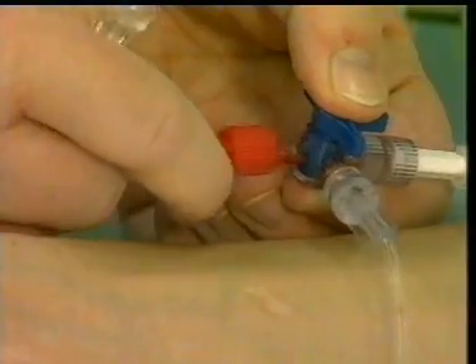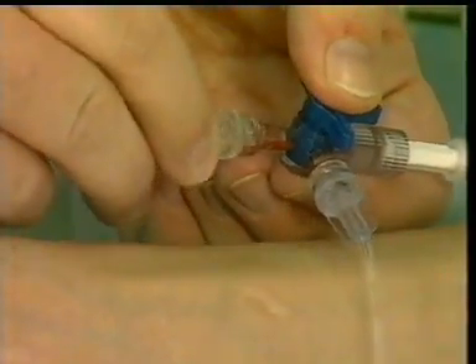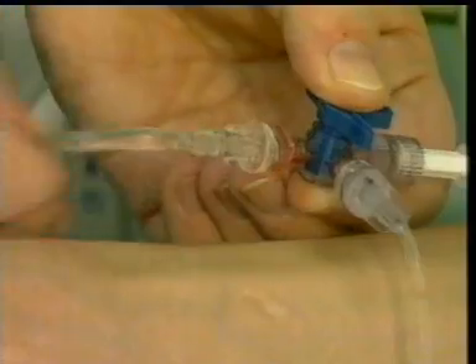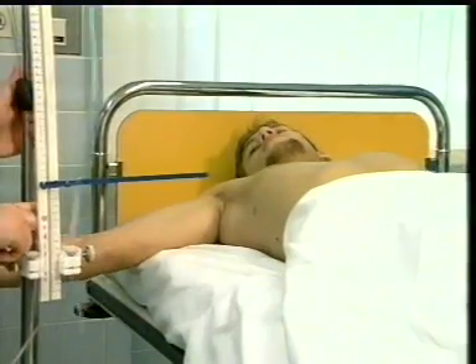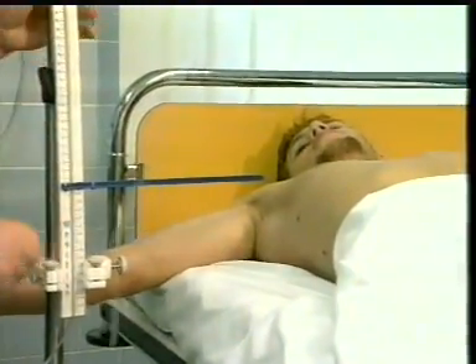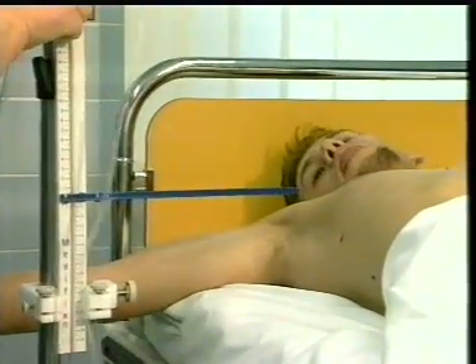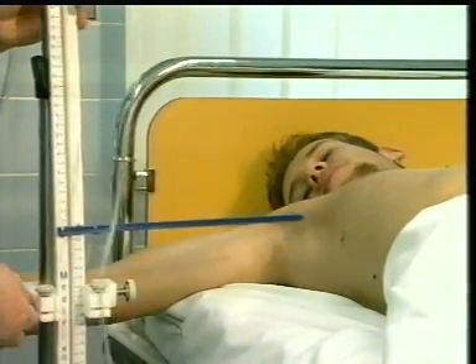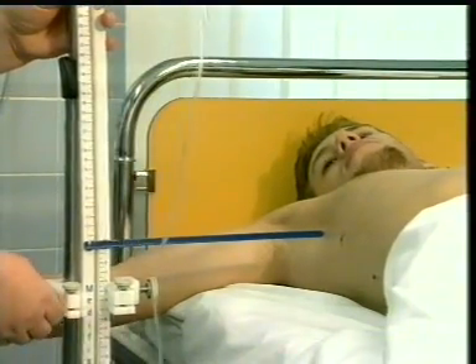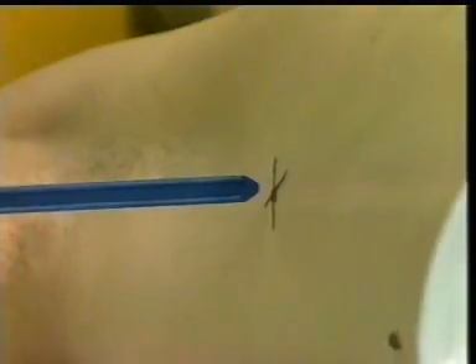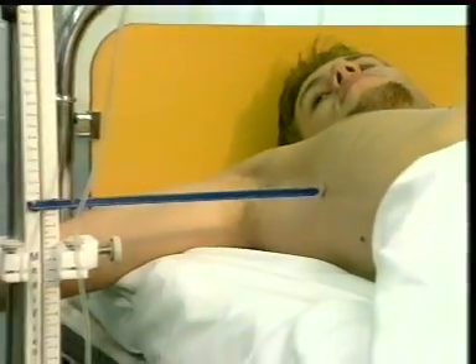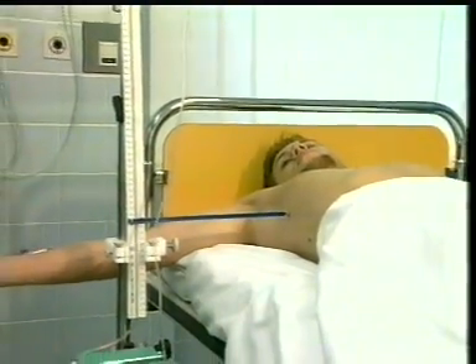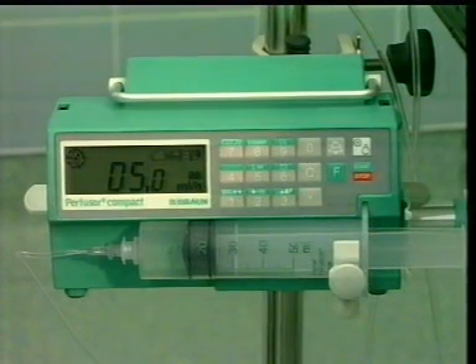The CVP set connection tube is connected to the central venous catheter. For the measurement, the Medifix Manometer Scale is brought into alignment with the 0 point. Because the infusion is interrupted by this process, the infusion pump must be switched off. Not all pumps have a standby mode for this situation like the one shown here. Many infusion pumps must be shut down and then reset when they're turned on again.